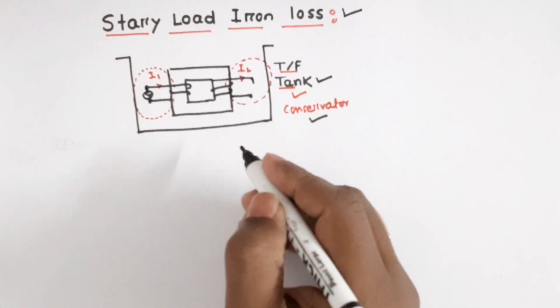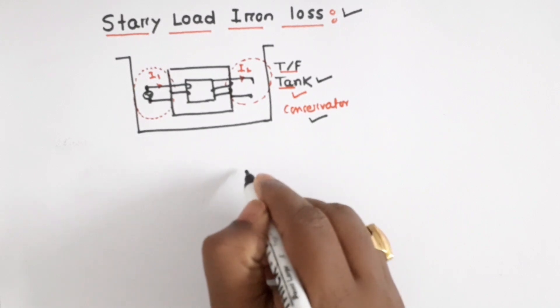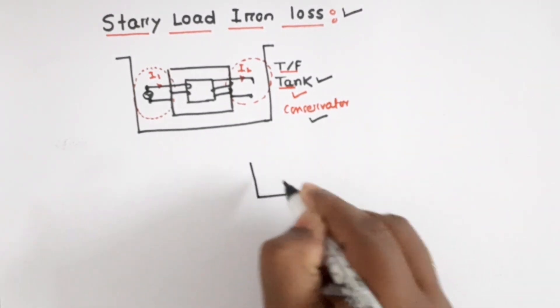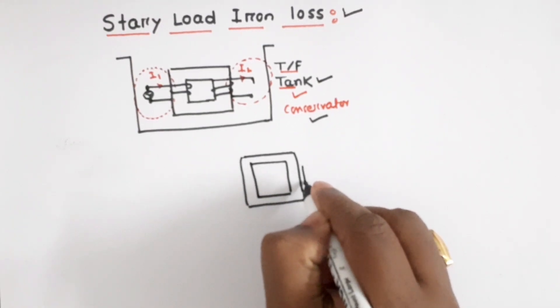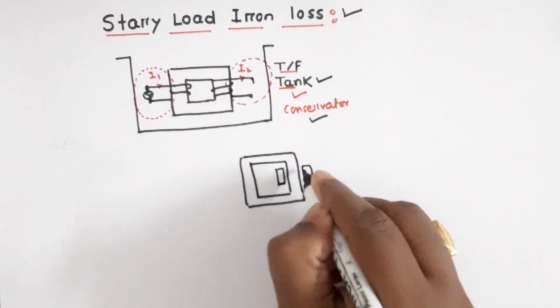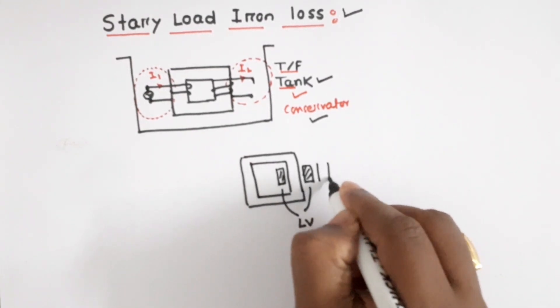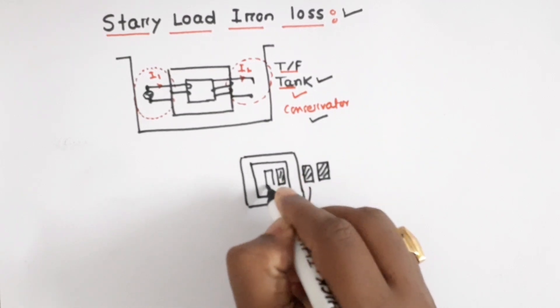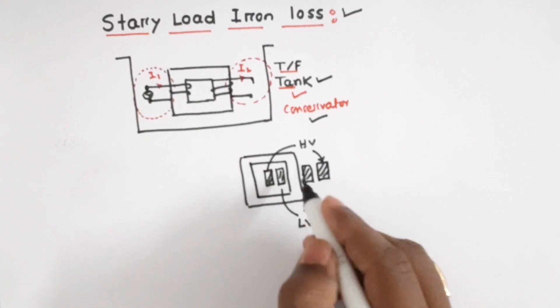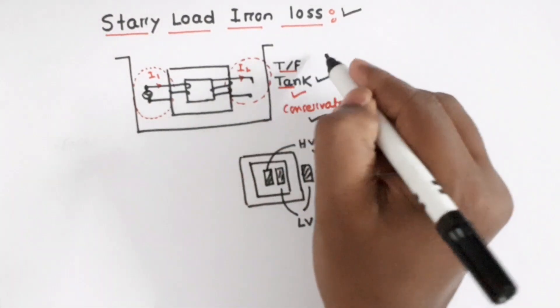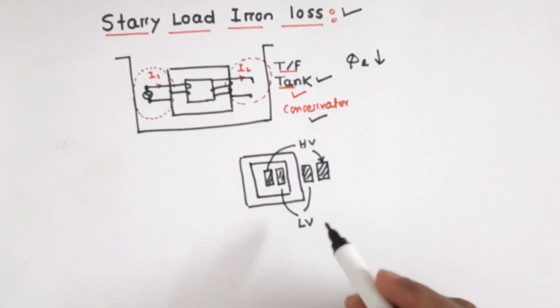To reduce the stray load iron loss in the core type transformer, an interleaved nature of winding is used. In the core type transformer, near the core we place the low voltage winding, and above the low voltage winding we place the high voltage winding. This is called interleaved nature of winding. Due to this interleaved winding, the leakage flux phi-L will be reduced, and therefore the stray load iron loss will also be reduced.